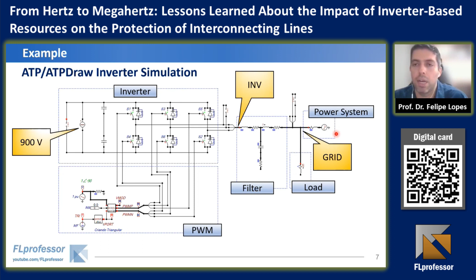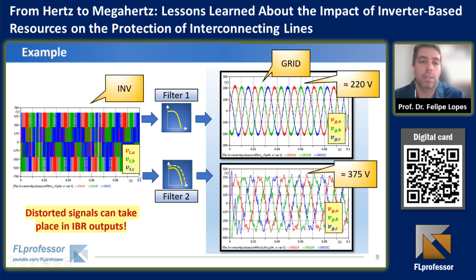These are the signals that we obtain by making this model, by simulating this system. These are the voltages from the phase to the ground measured at the inverter terminal. And to demonstrate the importance of these filters, I decided to implement two types of filters which I took from the literature. And here we can see that different distortions can take place in these signals. Regarding the amplitude, these amplitudes can also be different. It will depend on these filters. So distorted signals can take place in IBR outputs. This was another learning that we had at that time.